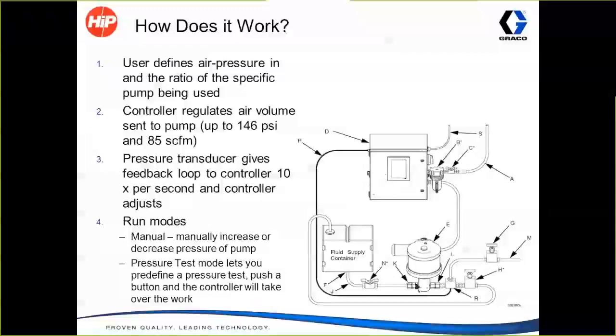On the outlet of the pump, we install a pressure transducer. So we also monitor the actual fluid pressure that that pump is generating. We send that signal back into the control box, and based on the reading of that pressure, we'll know we're either above or below the target, and we'll adjust the pump accordingly. So what we actually do is we do that measure and test function very quickly. We do that about 10 times per second, and we'll constantly adjust that pump to ultimately drive it up to a specific test pressure that you're asking for.